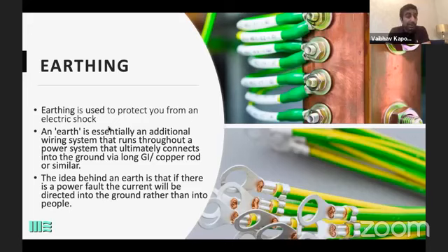What is earthing doing? Earthing is used to protect you from an electric shock. And earth is essentially an additional wiring system that runs throughout the power system, that ultimately connects into the ground via long GI or copper rods or similar. So like we saw in the first slide, there was a bucket earth, a small wire which was connected to the neutral wire. Neutral is always earth. There are two types of earths which we do everywhere, in permanent or temporary installations with gensets and all. One is the neutral earth, which you have to remember, and the second is the body earth.